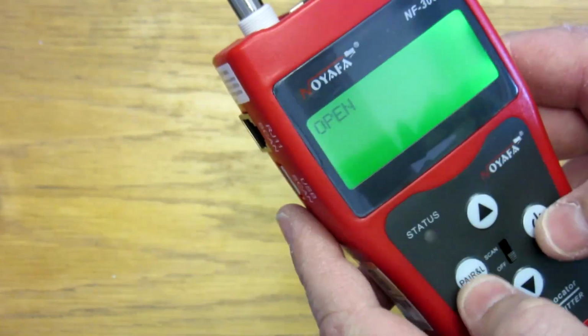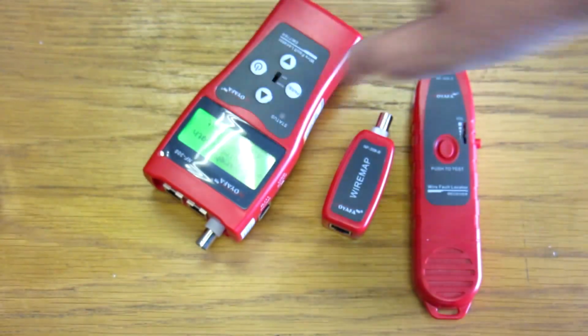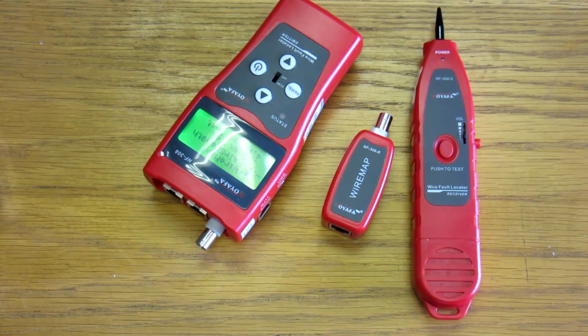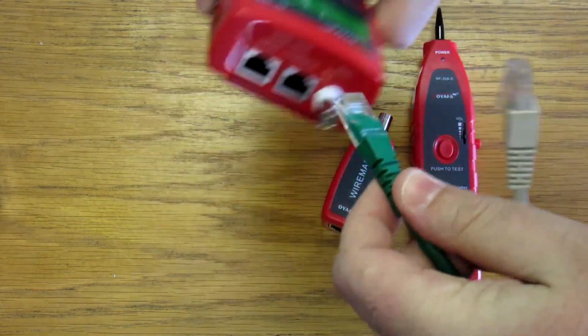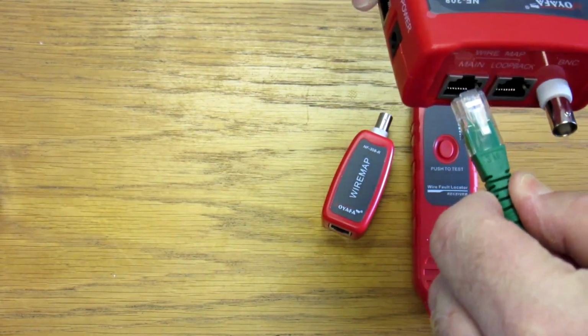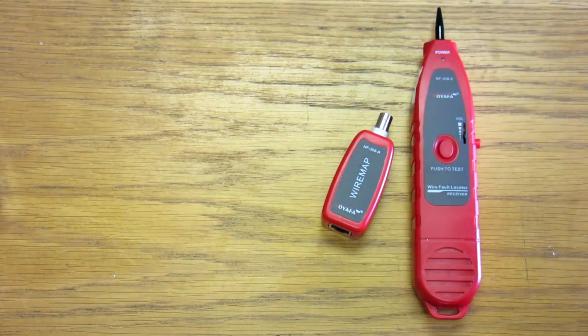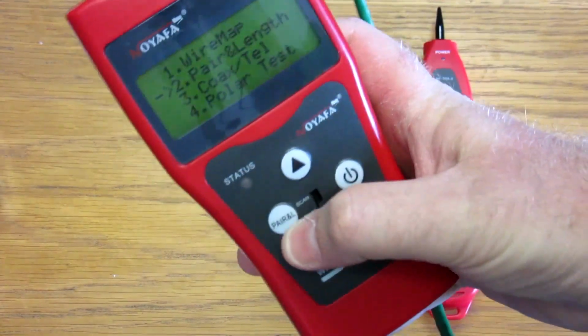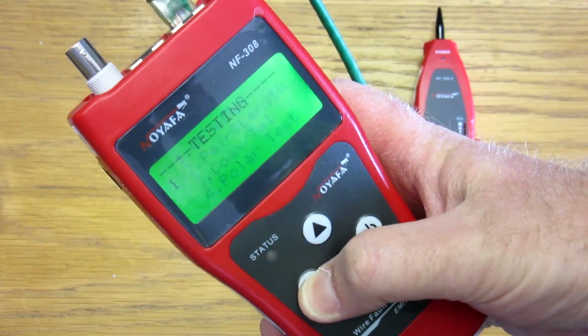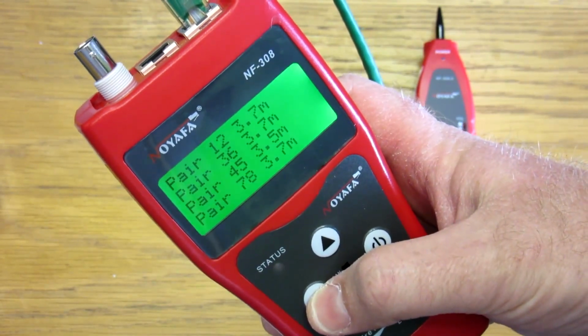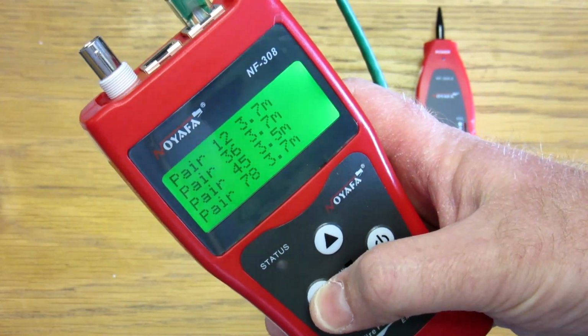So what we're going to do is get a longer piece of cable here. I've got two lengths, now bear in mind I haven't calibrated. One length, the green one, is around 4 meters. So we plug it into main, it's not terminated on the other side. Okay, and we can go pair and length, it'll test, and there you've got your 3.7 meters.